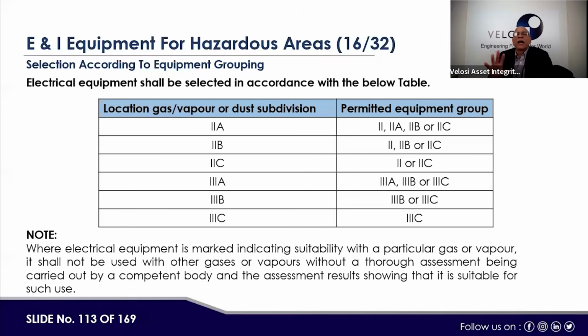Now, for the gas group, the selection according to equipment grouping: electrical equipment shall be selected in accordance with the table below. For example, the location gas or vapor 2A, 2B, 2C, 3A, 3B, 3C, and then the permitted equipment in the group which is applicable in that particular area can be used. Where electrical equipment is marked indicating suitability with a particular gas or vapor, it shall not be used with other gases or vapors without a thorough assessment being carried out.